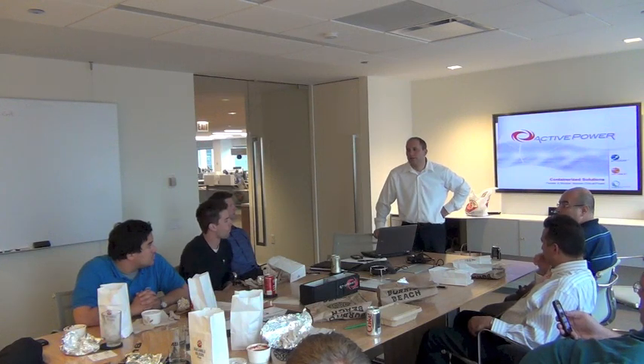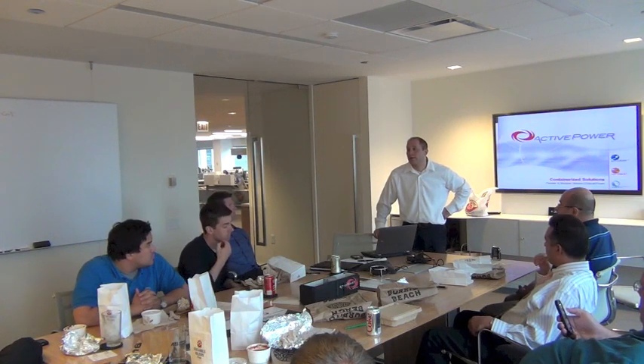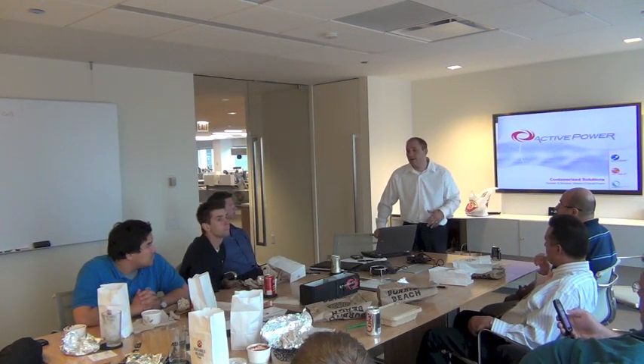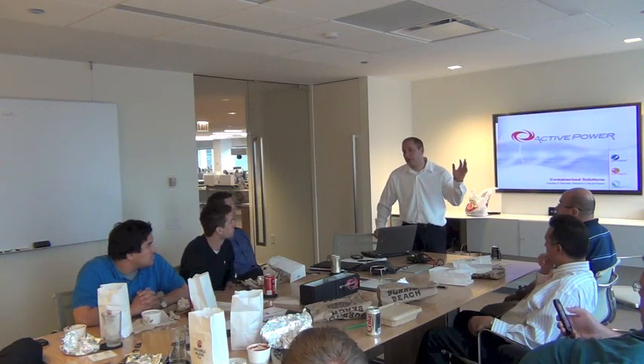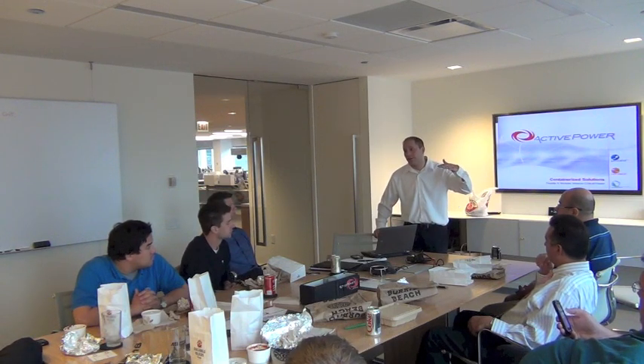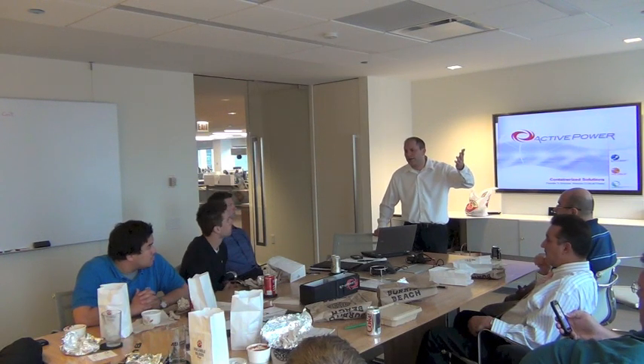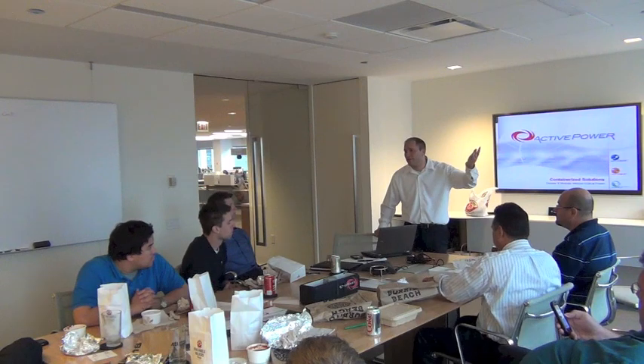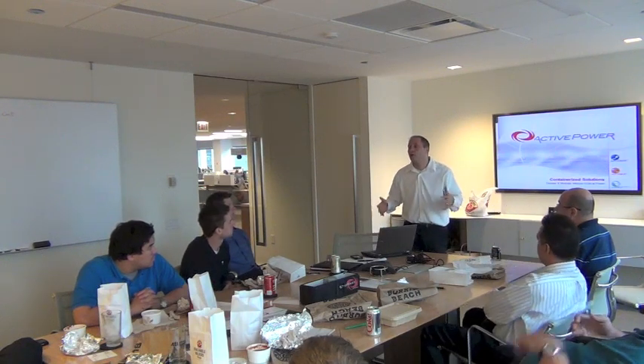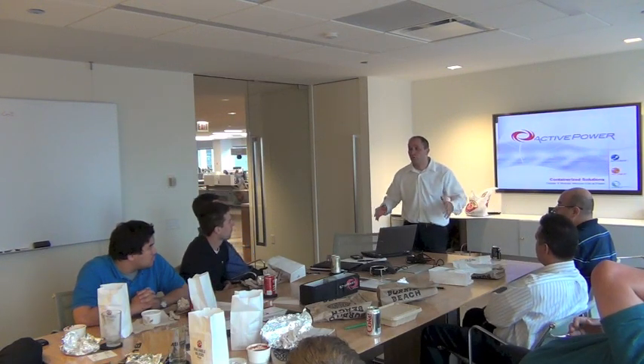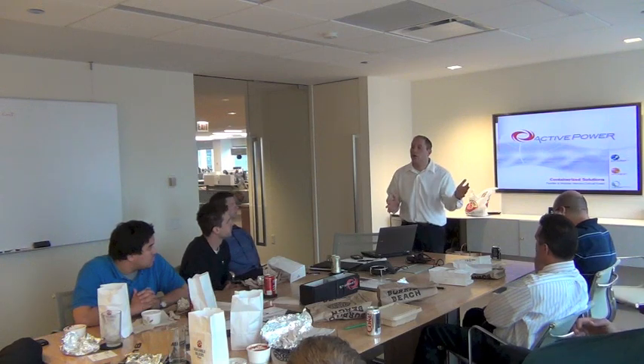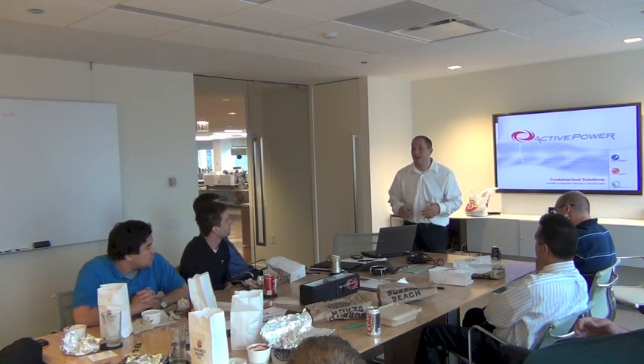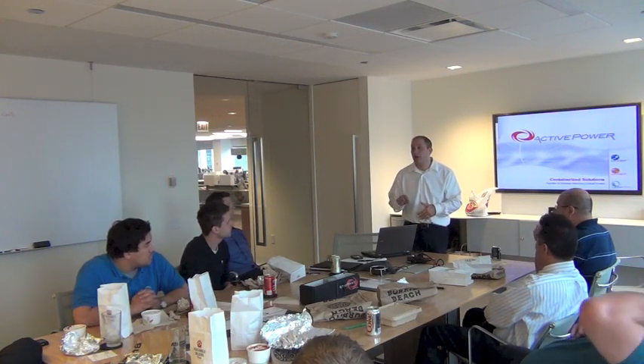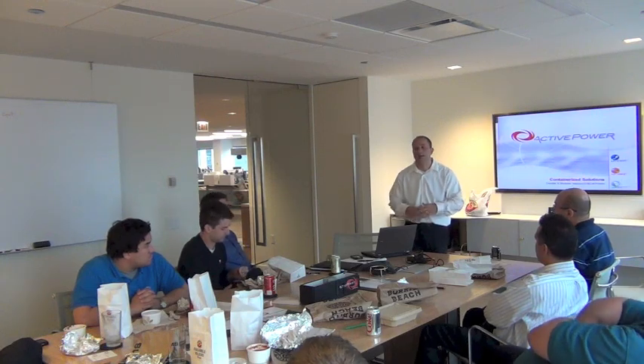As soon as we're on generator, whether we step loaded the generator, let's say we ran out of ride through time and walked on 80% of the load, we're going to put a 20% step load on the generator. The generator can take a step load. Ideally, you don't want to run out of ride through time and walk in. When we design a system, we want to make sure all the load is walked on before we're out of flywheel energy. And we're really good at poking our nose into the overall design and sequence of operation.